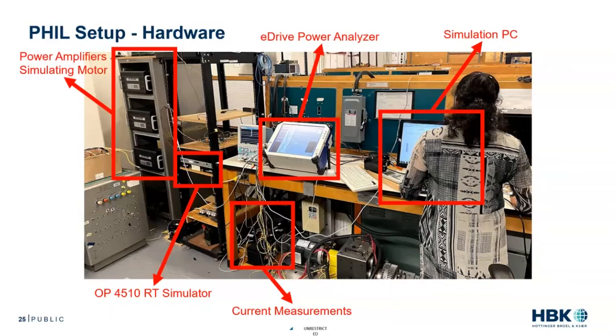So we're going to be executing a series of tests on this motor, line starts, load steps, and seeing how that simulated motor responds to those grid events. So we have measurement, we have simulation, we have emulation with these power amplifiers, and we have some really nice measurement systems.